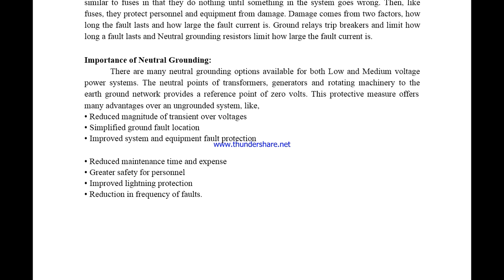So let us consider the importance of neutral grounding first. It can be used for both low and medium voltage. It can protect transformers, generators, rotating machinery, etc., because they may have the star connection where the neutral is present. To the earth ground network, it provides the reference point of 0 volt. This protective measure offers advantages like reduced magnitude of transient voltages, simplified ground fault location, improved protection level, reduced maintenance time and cost, greater safety for personnel, improved lightning protection, and reduction in the frequency of fault occurrence.